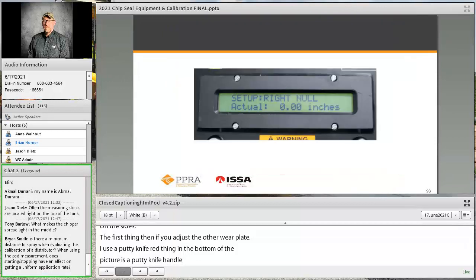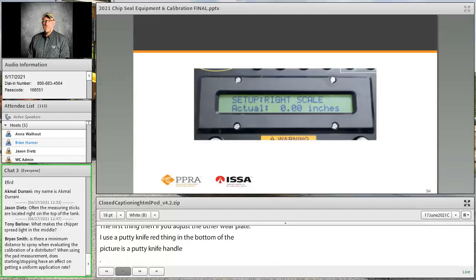So you want to go through and adjust all those. Then you have to actually go into the computer. You did all the manual adjustments, and this is all part of calibration. After the manual adjustments, you have to go in and do what we call the null and the scale. That's basically fancy words for telling the computer where closed and full open is. So now my computer knows my gate is closed at this point, and if I open it all the way up, it's open to a certain point—4 inches on most hoppers.